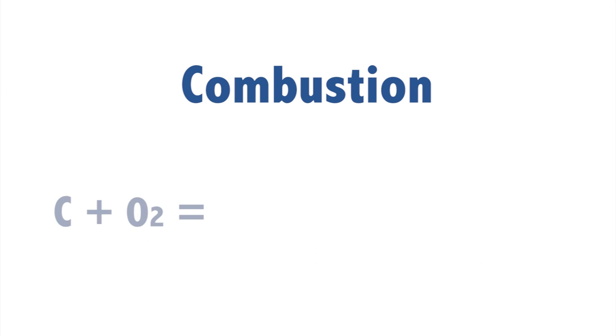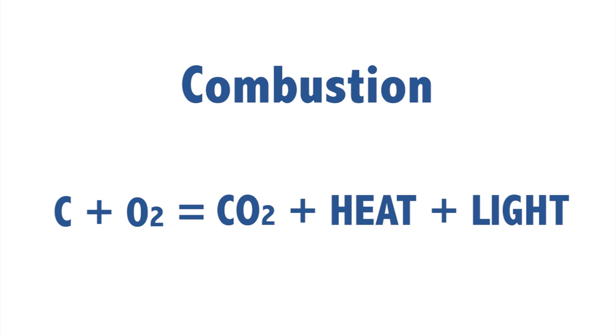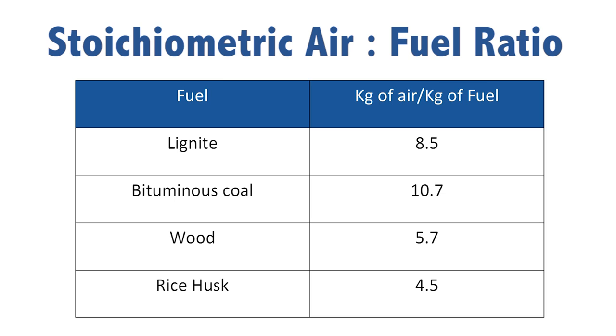When combustion takes place in a boiler, the carbon reacts with oxygen in the air to form carbon dioxide, and along with it releases heat and light. Now for carbon to completely burn, a certain amount of air is required — that is basically the stoichiometric air to fuel ratio. In practice, if we supply the stoichiometric air, it is not possible that the carbon fully combusts, because in the time available for combustion in a boiler, it is impossible that every molecule of oxygen gets one molecule of carbon and both of them combust. So in practice, a certain amount of excess air is required.